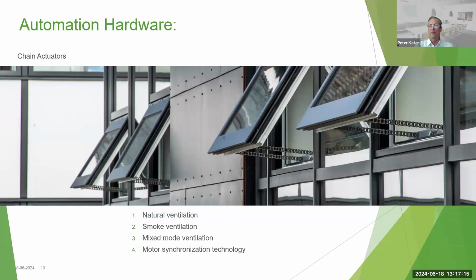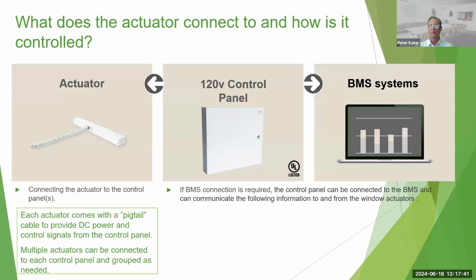These chains are unidirectional. That means they only bend in one direction. But because the body of the actuator is fixed and the point where it attaches to the sash is fixed, they operate as if they were a rigid element, even though when the chain retracts, it can curl up inside the actuator body for storage. So the actuator is basically just an electric motor driving a chain in and out of the body, as you can see here.